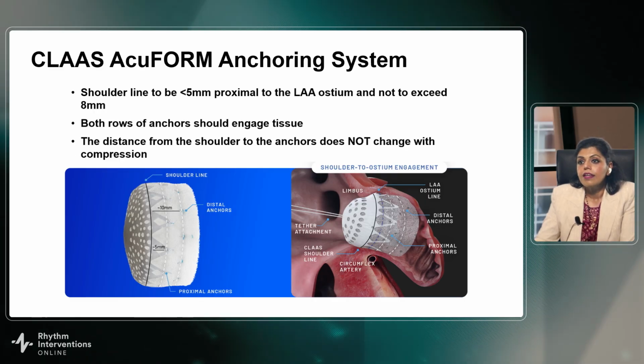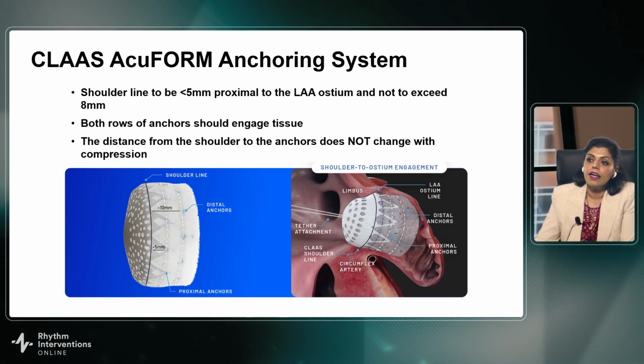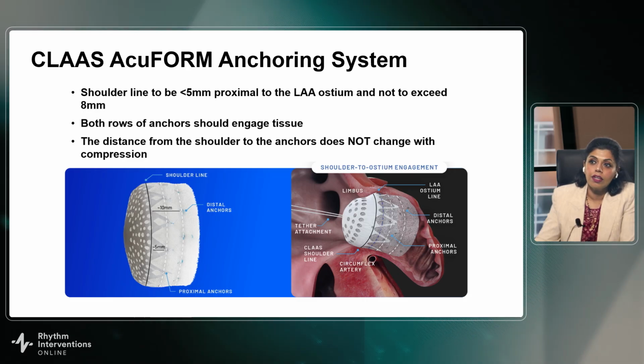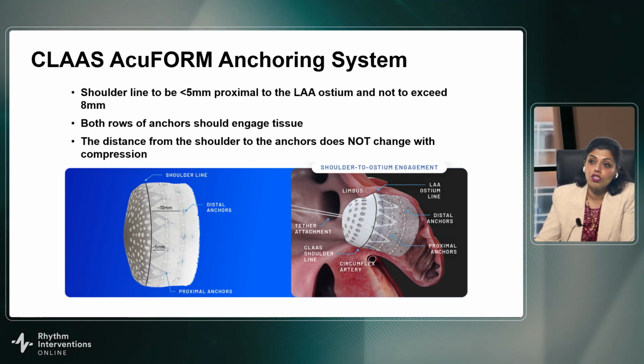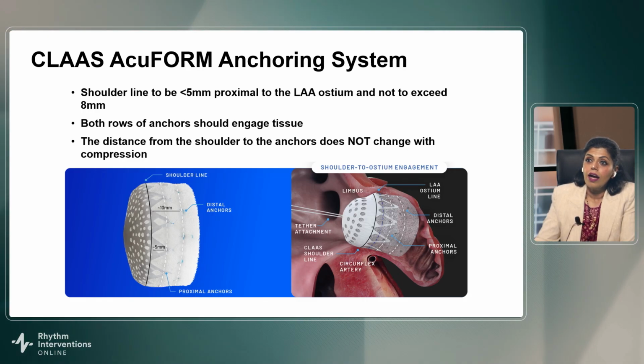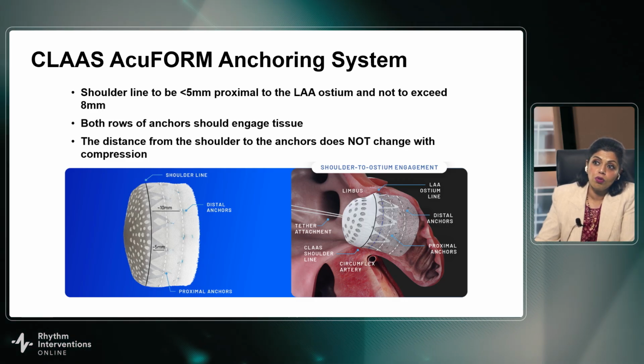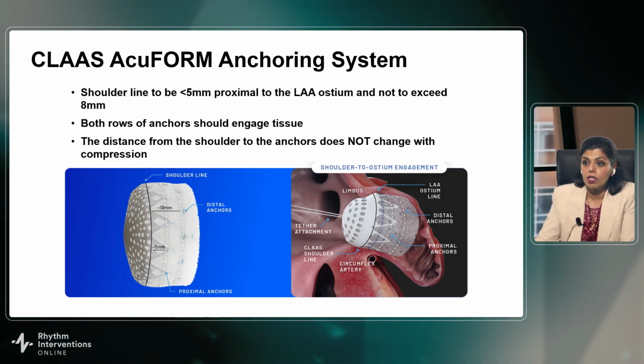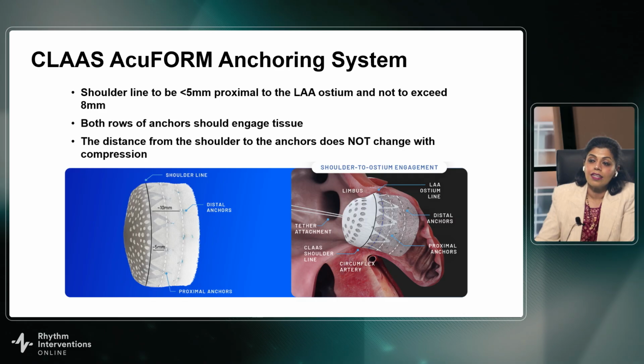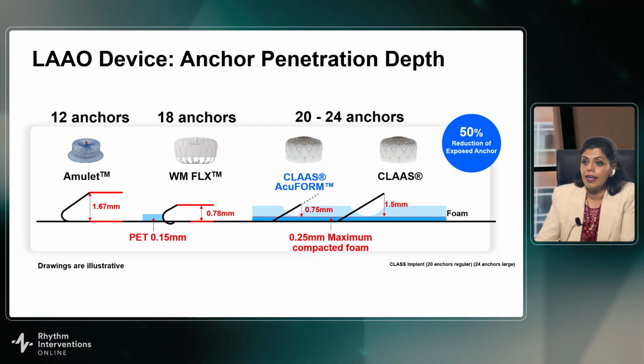Now, one of the things about the anchoring system, the system did undergo some recent changes. This is a newer version, the Accuform device, and what was changed was the anchoring of the system. So now there's two rows of anchors. The distance from the shoulder to the anchors really does not change with the compression. So the idea is that the foam expands and conforms to the appendage, and the two rows of anchors are able to engage the tissue.